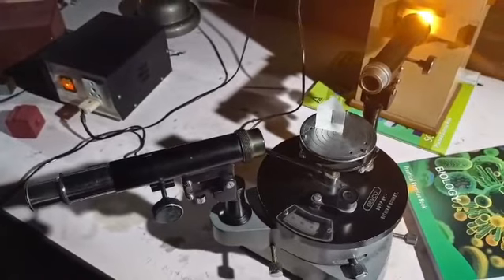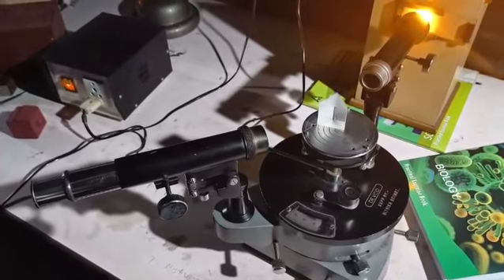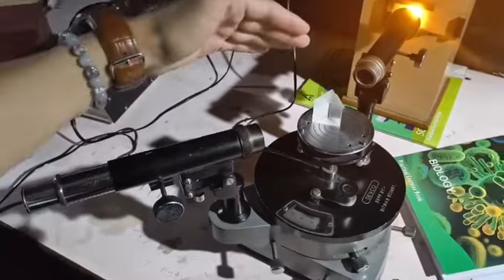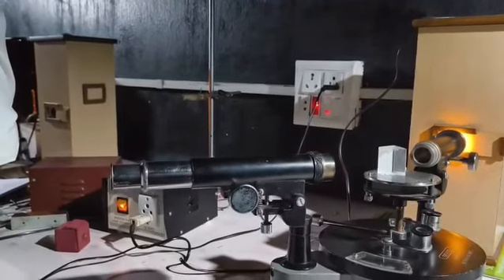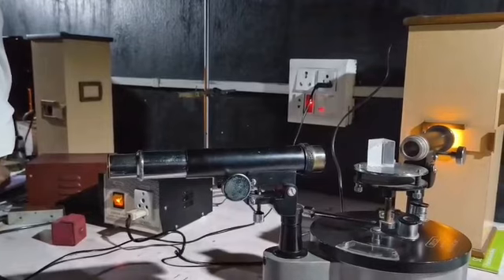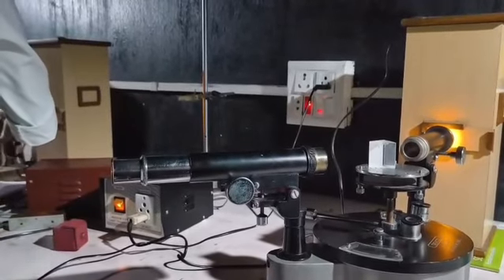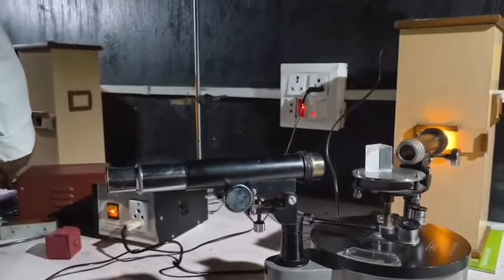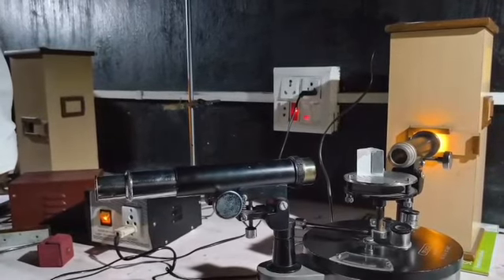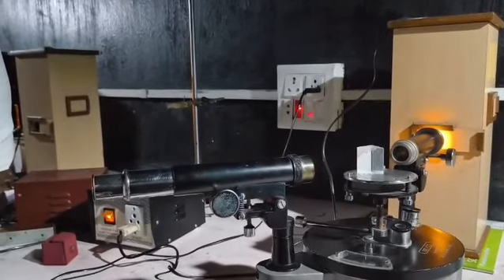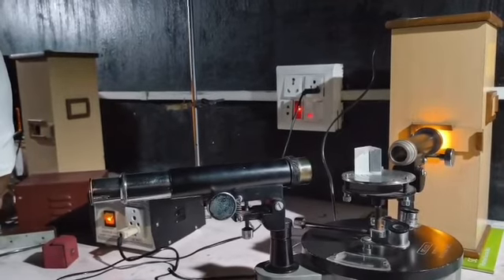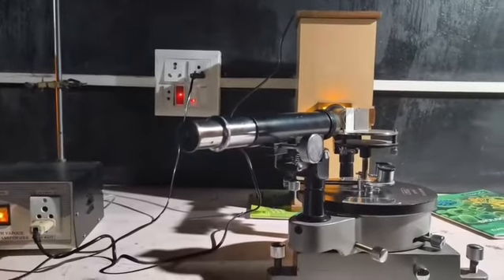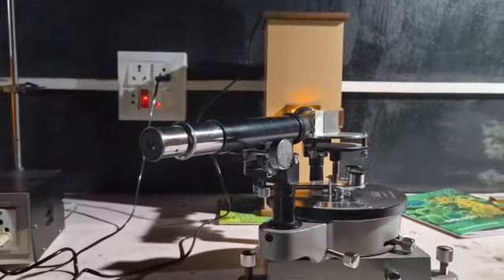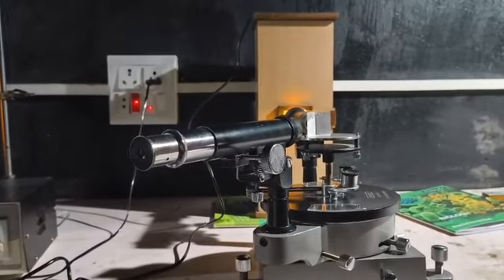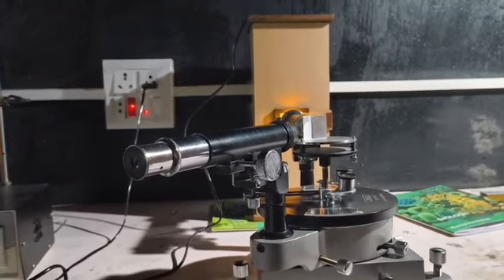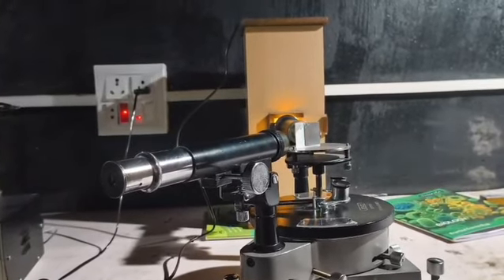Now we have to find the minimum deviation of the sodium light through this prism. The next step is to find the position of minimum deviation. How can we find it? In order to find the position of minimum deviation, we have to rotate the base of the spectrometer and simultaneously observe the spectral line through the telescope. In order to take the reading, we have to adjust the spectral lines to the minimum deviation position, that is, the position where the spectral lines move towards the opposite direction.